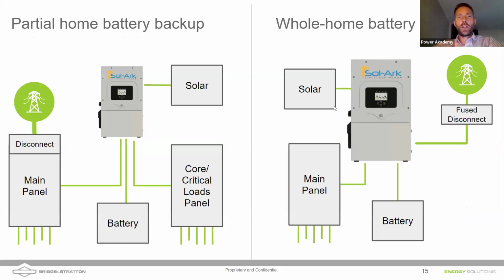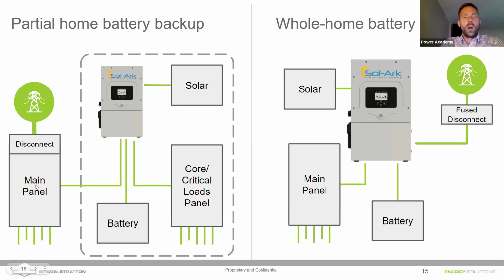So what exactly do we mean by whole home backup versus a partial home backup? Historically, a typical system would be what you have on the left side of the screen, right? This partial home backup. And this might be a Sol-Ark 8K or a 12K inverter with that 63 amps of pass-through. So you would feed that inverter through a breaker in your main loads panel. And then if the grid were to go down, the inverter would isolate itself from that main panel. So it would open a relay inside the inverter to make sure we're not feeding any power back to that main panel and back up onto the grid where linemen might be working.